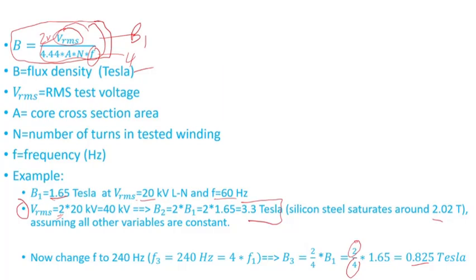That's one of the reasons why during the induced voltage test the frequency is increased—because the voltage is increased. And since the flux density is proportional to volts per turn, that means if you increase the voltage, you must increase the number of turns to avoid saturation, or...